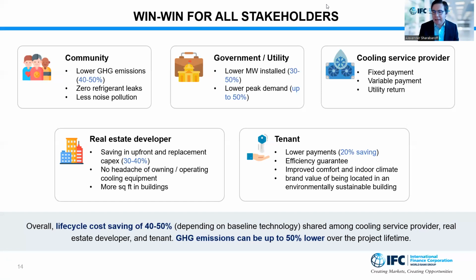Typically, the condition is referenced as a minimum density of a cooling load of 8,000 to 10,000 refrigeration tons per square kilometer. And then you need to have an adequate number of equivalent full load hours, so you need a concentrated demand for an extended period of time.